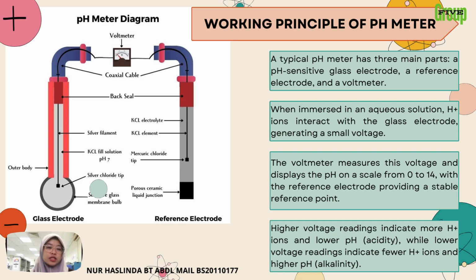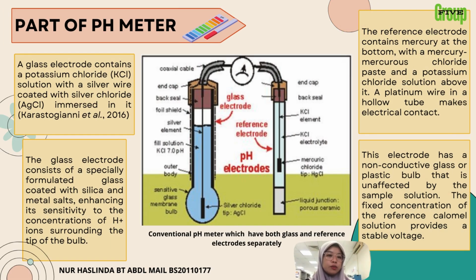Higher voltage readings mean there's a higher concentration of H+ ions, indicating a more acidic solution, a lower pH value. Lower readings suggest fewer H+ ions and more OH- ions, indicating a more alkaline solution, a higher pH value. This way, the pH meter accurately determines how acidic or alkaline the solution is based on the voltage created by this electrode. In a conventional pH meter, you will find both the glass and reference electrodes separate from each other.